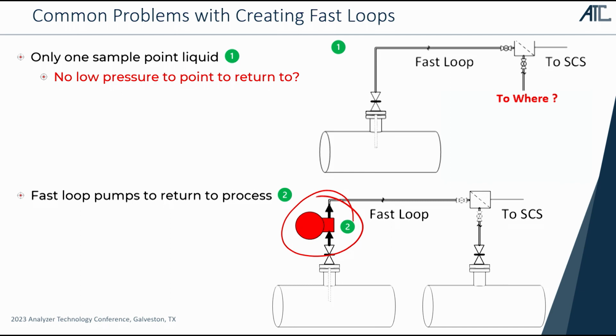It's easy, right? Well, as soon as we put in a pump, we have a whole bunch of issues that can potentially arise with that. First of all, process pumps are going to be expensive. So we're going to have costs associated with the pump. We're going to probably have a lot more maintenance because pumps require maintenance. When we're looking at analyzer installations, I frequently say, I don't like to put pumps in because I make my analyzer mechanics become pump mechanics.